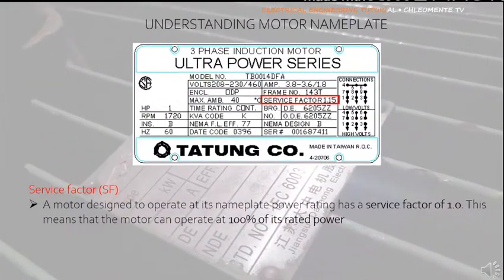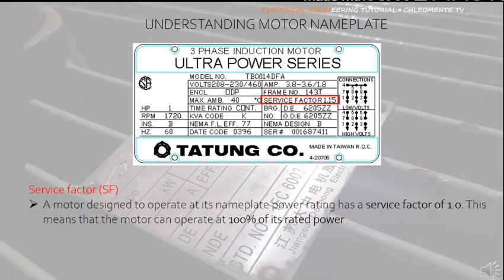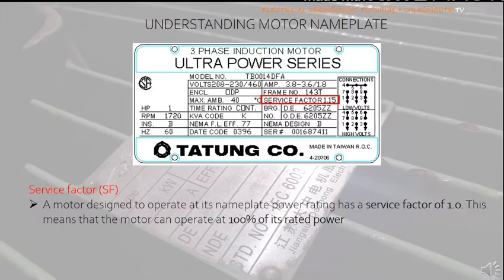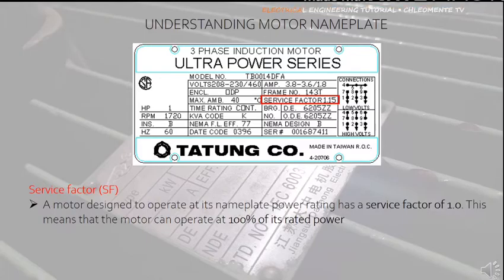Service Factor, denoted by SF: A motor designed to operate at its nameplate power rating has a service factor of 1.0, meaning it can operate at 100% of its rated power. In this example, a service factor of 1.15 means you can operate the motor at 115% of its rated power — so this motor can operate at a maximum of 1.15 horsepower.